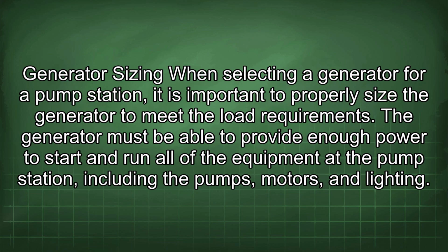Generator sizing. When selecting a generator for a pump station, it is important to properly size the generator to meet the load requirements. The generator must be able to provide enough power to start and run all of the equipment at the pump station, including the pumps, motors, and lighting.